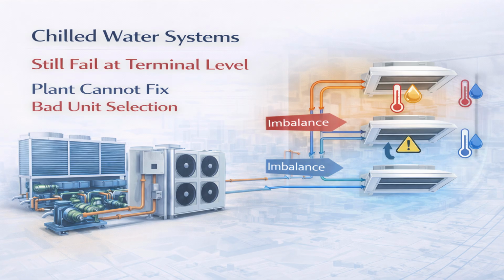This leads to poor temperature control and inconsistent comfort across spaces. The central plant continues to operate, but it cannot correct the terminal level problems. In other words, the plant can supply chilled water, but it cannot fix poor heat exchange, bad valve authority, or incorrect coil selection. This is why even in chilled water systems, good terminal unit selection is just as important as plant design.